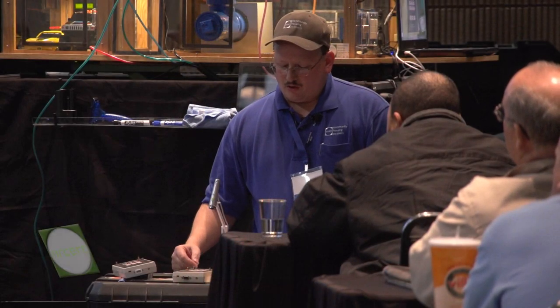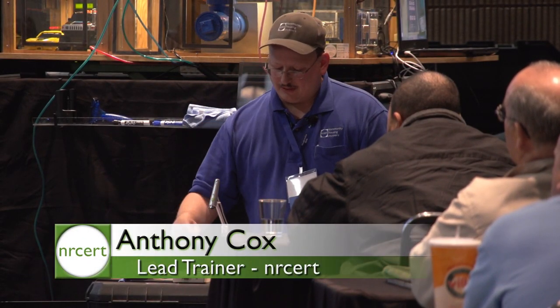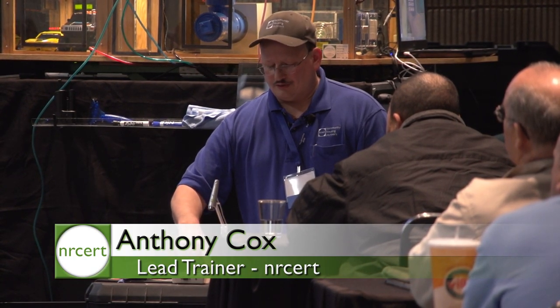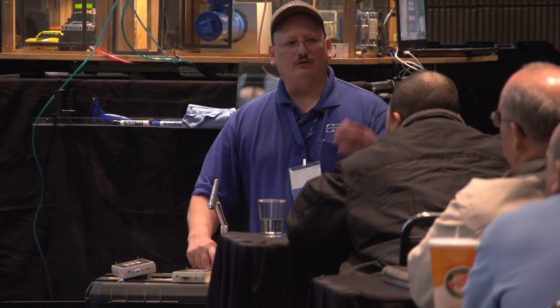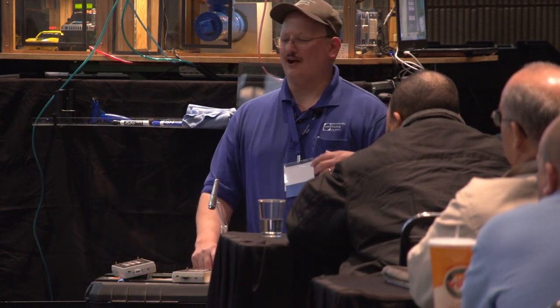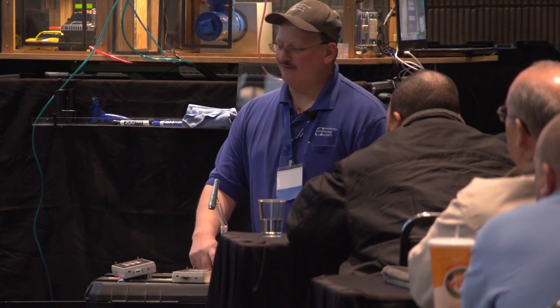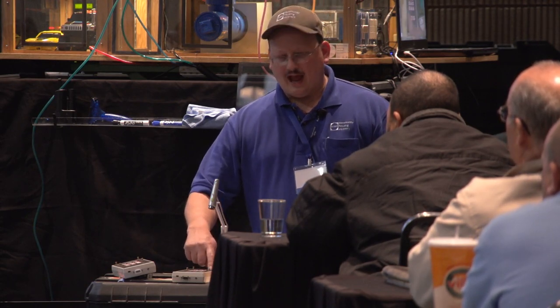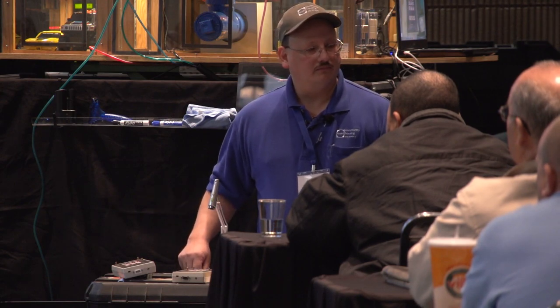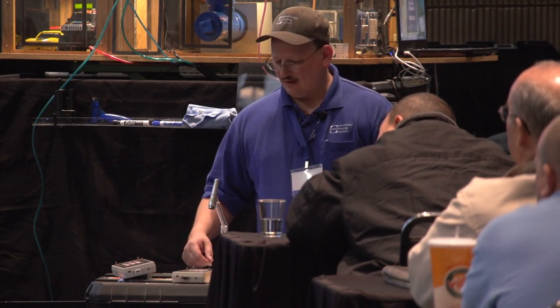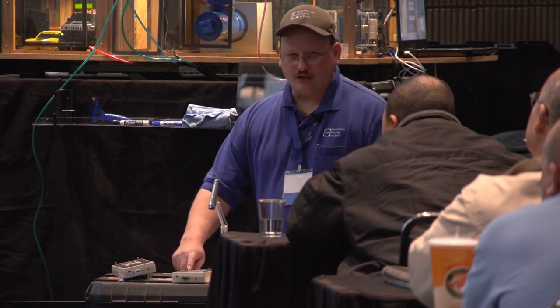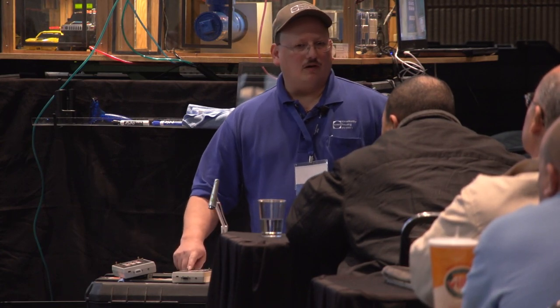When you do the blower door, what do you typically measure? You usually put it on channel A. What do you do with the top port? It stays open, right? What about the bottom port? It's usually a hose that goes to the outside. And if you were talking to somebody, in what they call manometer language, you would say house with reference to what? Outside, right?